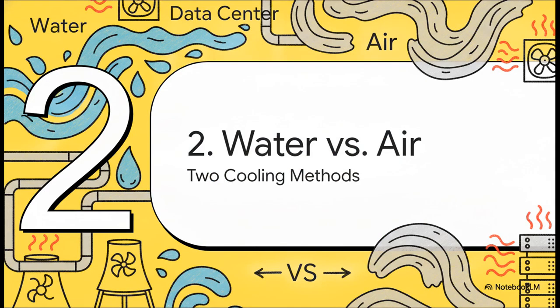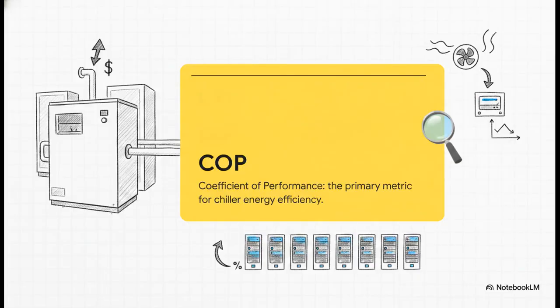Moving on to Section 2, water versus air cooling. To solve this monumental heat problem, engineers basically have to choose between two main cooling methods, water or air. But before we compare those, we really need to understand a vital metric called COP, or the coefficient of performance. Maximizing this efficiency metric is the ultimate goal for any facility operator out there. Simply put, a higher COP means the chiller is doing a much better job of removing heat while using way less electricity. And when you're operating at the scale of a hyperscale data center, even a tiny fractional improvement in your COP can save millions of dollars in energy costs.